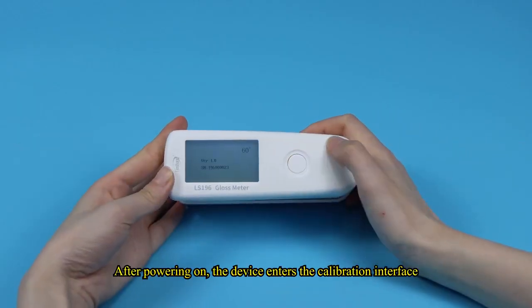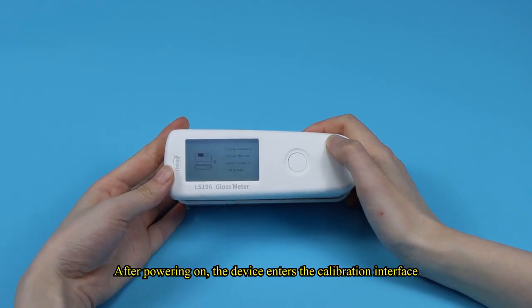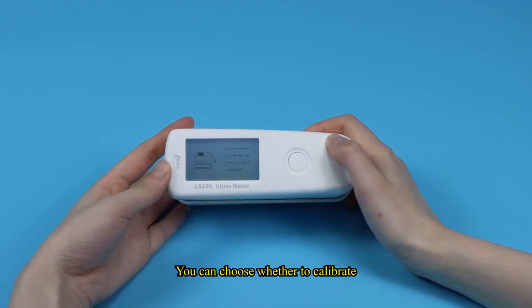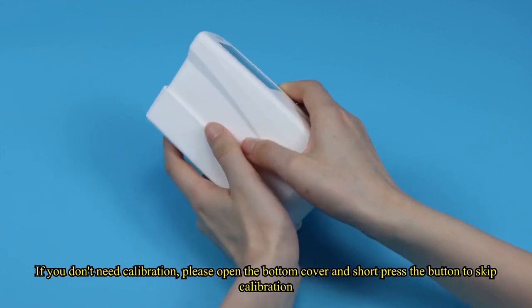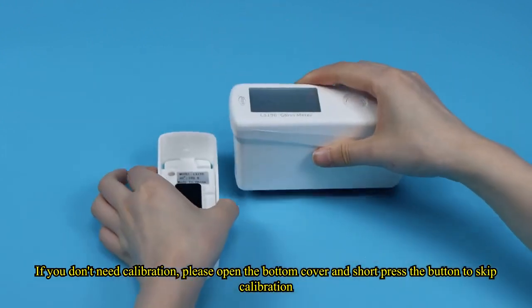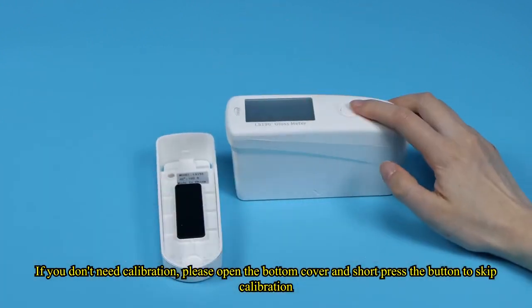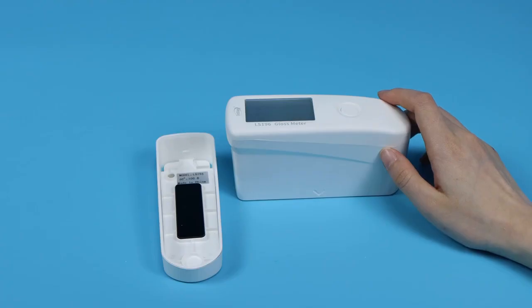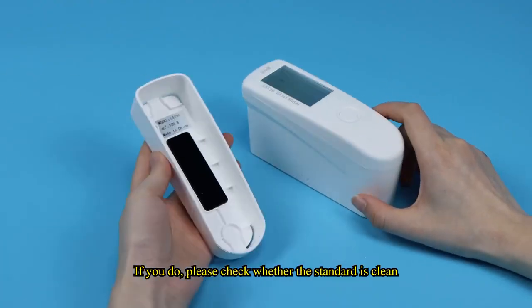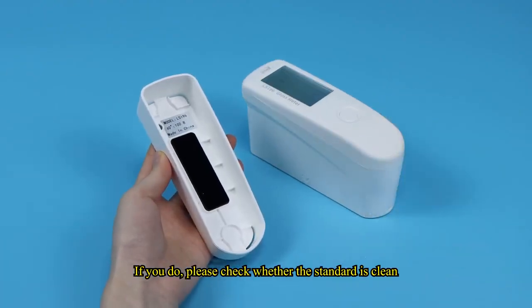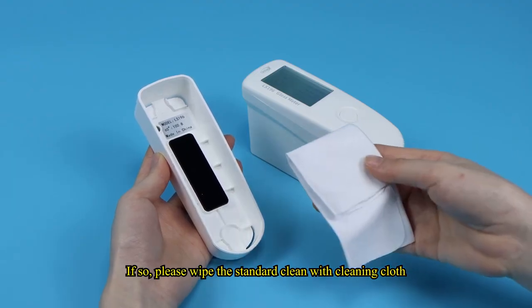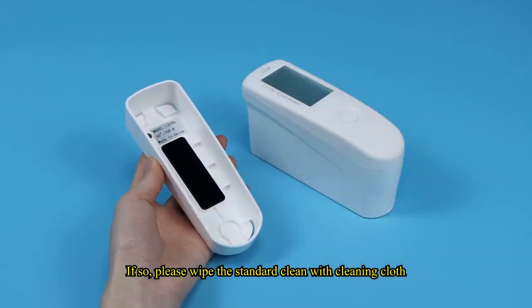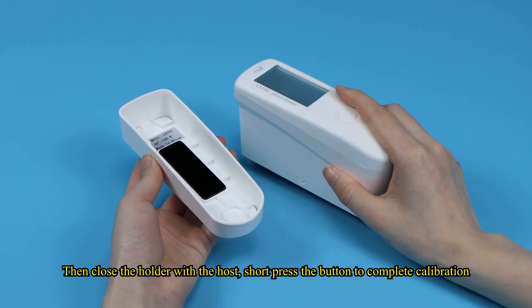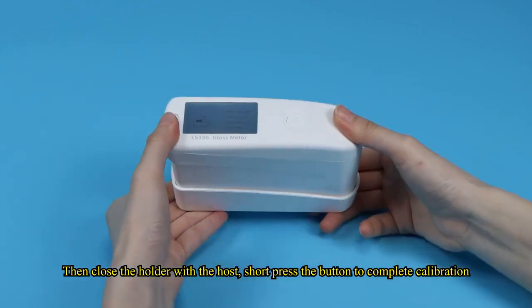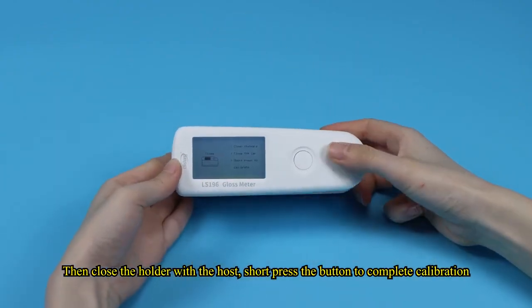After powering on, the device enters the calibration interface. You can choose whether to calibrate. If you don't need calibration, please open the bottom cover and short press the button to skip calibration. If you do, please check whether the standard is clean. If not, please wipe the standard clean with the cleaning cloth. Then close the holder with the host, short press the button to complete calibration.